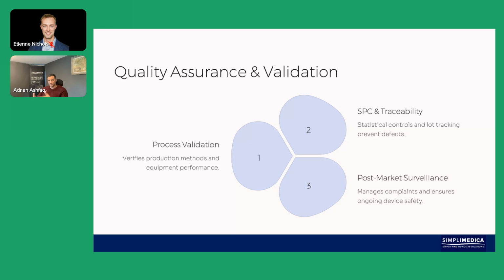So if you're doing an IQ, OQ, PQ, the OQ is often known as operational qualification. I'm going to throw in another OQ, which is optimization qualification, because you need to optimize your process before you get to operational qualification. That's like, do I know what the parameters are? I've got to do some design of experiments. Again, just to throw in one of the Japanese philosophers, Taguchi, if anyone knows Taguchi, there are Taguchi methods, which again is looking at orthogonal arrays, looking at different permutations. If you've got different elements like time, speed, temperature, humidity, you've got to look at different factors that would then give you a stable manufacturing process.